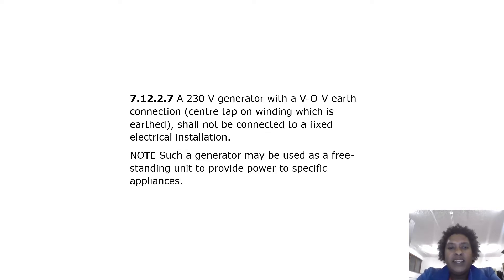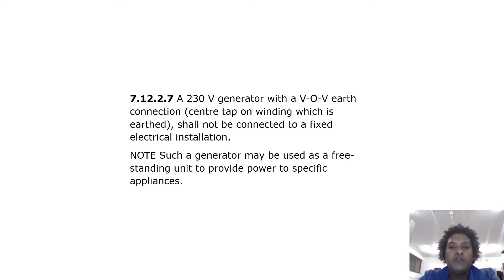A 230 volt generator with a mid-point earth connection — centre tap on winding which is earthed — shall not be connected to a fixed electrical installation. Note: such a generator may be used as a freestanding unit to provide power to specific appliances.